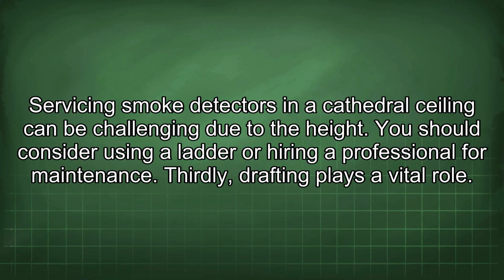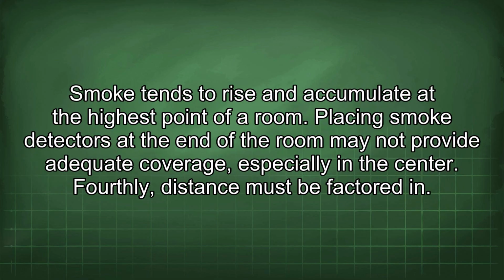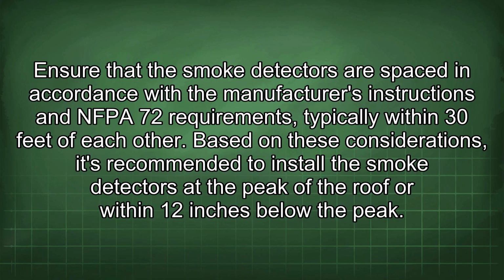Thirdly, drafting plays a vital role. Smoke tends to rise and accumulate at the highest point of a room. Placing smoke detectors at the end of the room may not provide adequate coverage, especially in the center. Fourthly, distance must be factored in. Ensure that the smoke detectors are spaced in accordance with the manufacturer's instructions and NFPA 72 requirements, typically within 30 feet of each other.